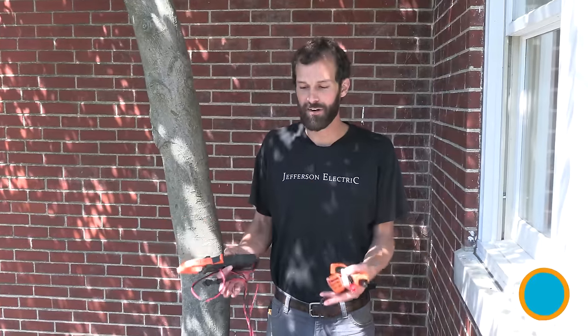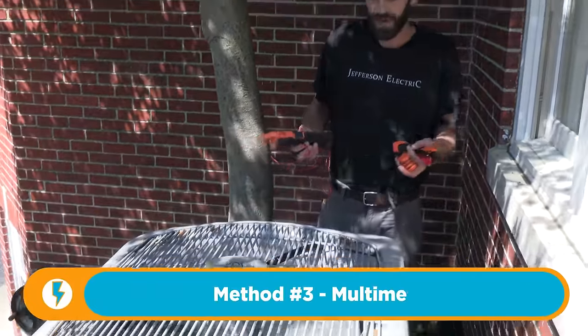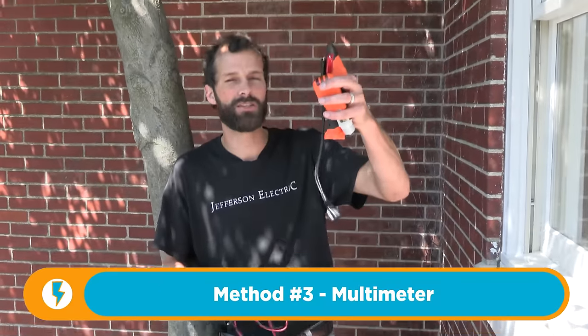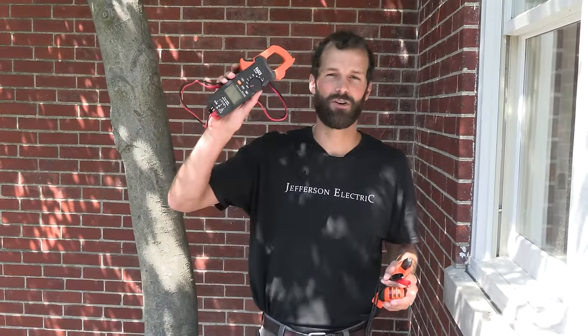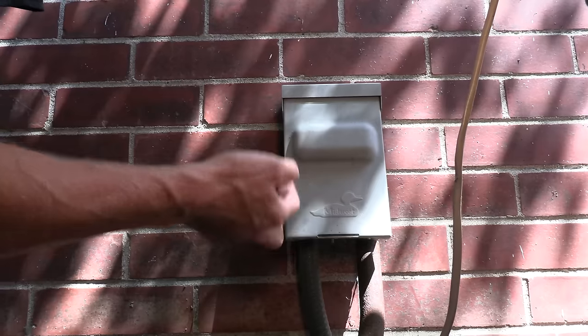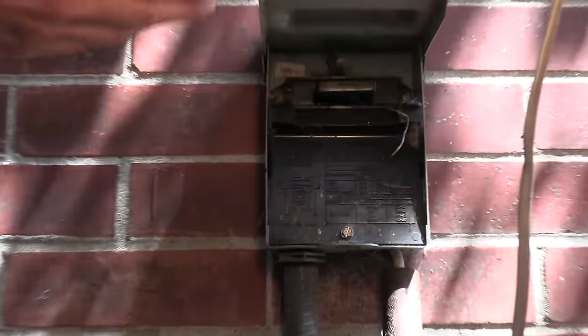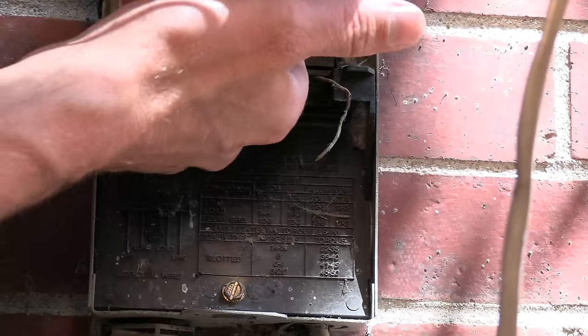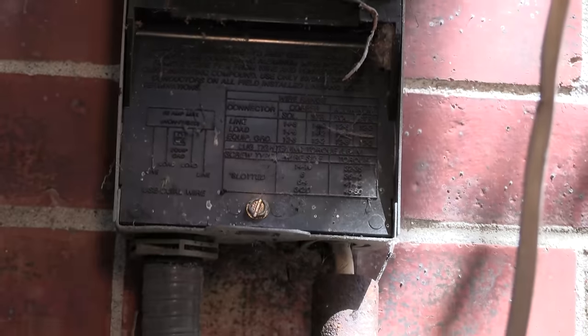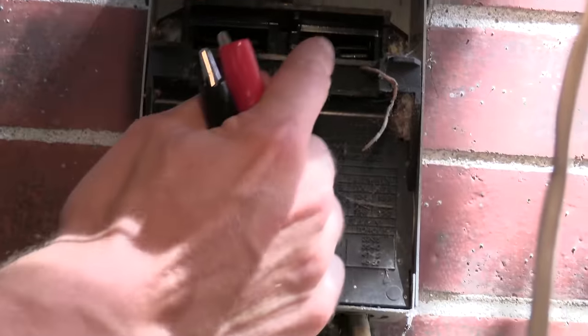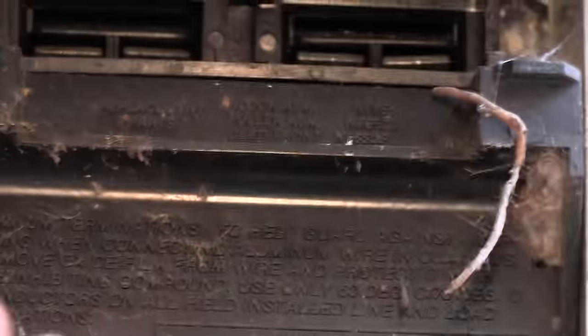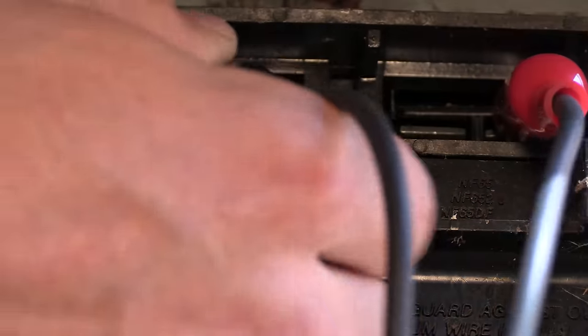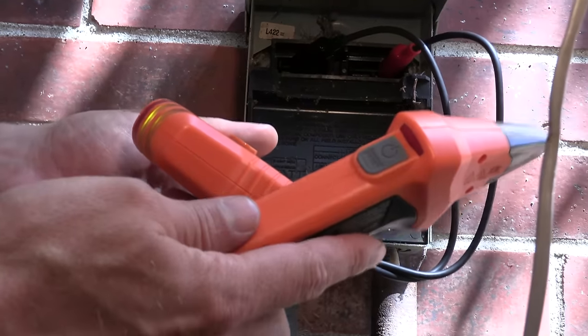Since the air conditioner is already running, it's easy to tell when it shuts off. But if it's not running, or you don't have a helper, what you can use is this trace tool or a digital multimeter to confirm loss of power. So now we're behind the air conditioner, and every air conditioner should have a disconnect. Many of them look just like this. And in that disconnect, there's going to be a pull-out. And in that pull-out, there's going to be two terminals on each side. What you're going to want to do, if it's wired properly, is connect to the outside set of terminals. So I've extended those alligator plugs, clips, and let's slip them in there. All right. And now you can see I'm connected. I can use my standard tool to go find the breaker.